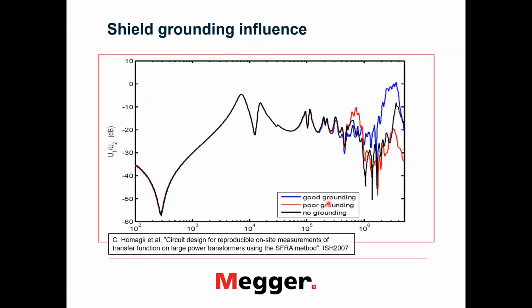So here I can illustrate the previous importance of shield grounding. We don't have any influence of that at lower frequencies, but above, let's say, 1 megahertz or below that even, we have quite a few differences when we have a good grounding, the blue curve. If we have a poor grounding, we have a red one, and the black one is when we don't have any grounding at all.